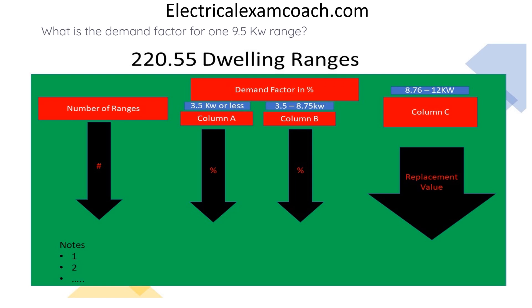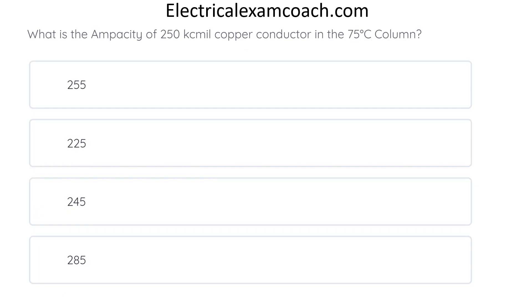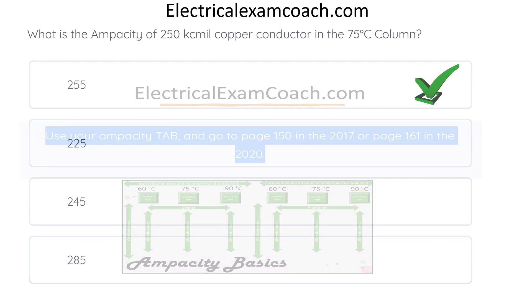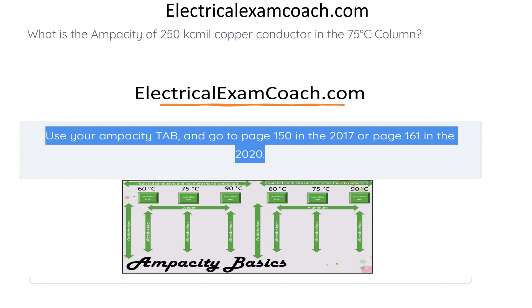So our 9.5 kW range only counts for 8 kW on our load calculation. Great job! What is the ampacity of a 250 kCMil copper conductor in the 75 degrees C column? The correct answer is 255 amps. When we head to our primary ampacity table, we're on the left-hand side because it's copper. We come down and find 250 kCMil, then cross over to the 75 degrees C column. We find that 250 kCMil copper is good for 255 amps in the 75 degrees C column.